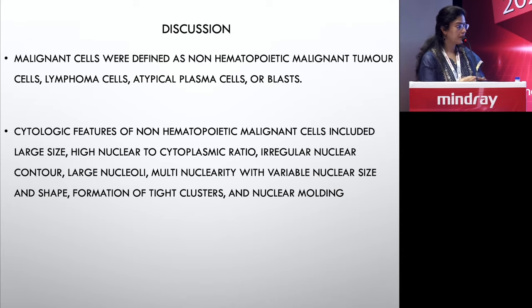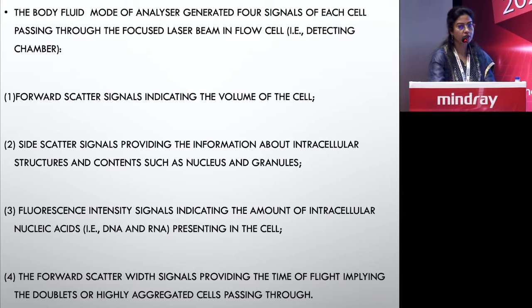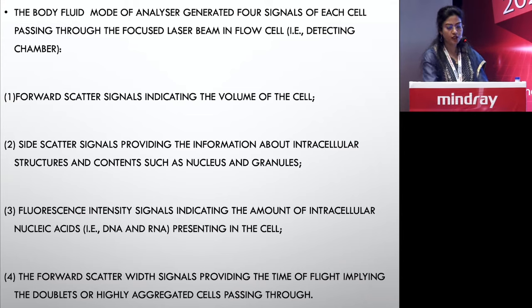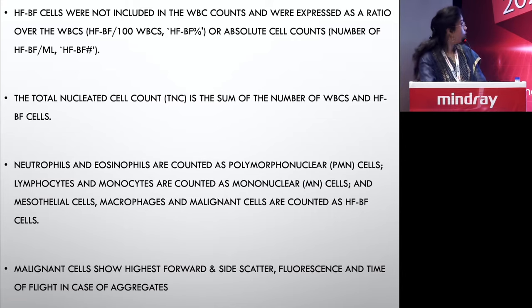In summary, automated analyzers attempt to pick up malignant cells but also pick up mesothelial cells, so both appear in the high fluorescent area. If you take only the forward scatter based on cell size, cancer cells — which have varied size and morphology — can sometimes be missed in the high fluorescent area, particularly if they are smaller.